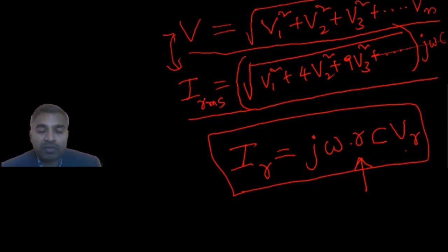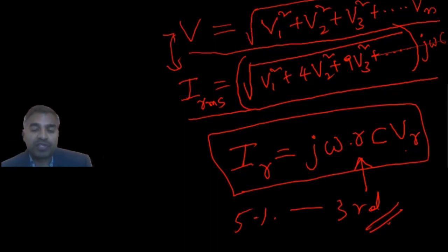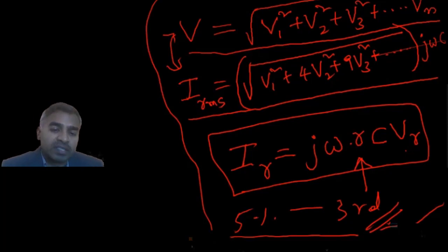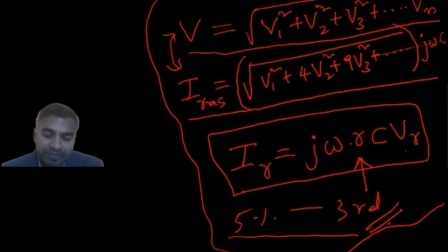You may calculate approximately how much error it will cause, for example assuming 5% of third harmonic. Harmonics like 1, 3, 5, 7 are normally present in the system, so you may compute an error. This is one of the problems with capacitance in series with ammeter.